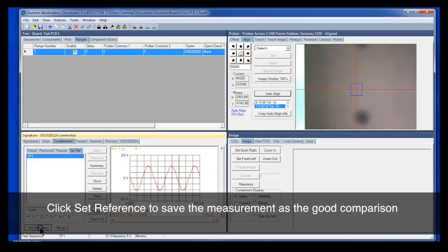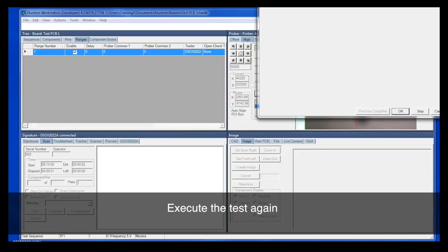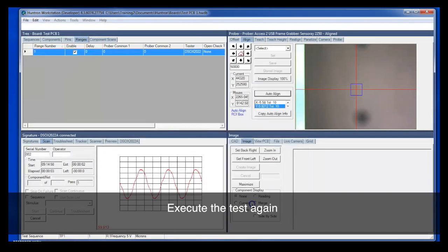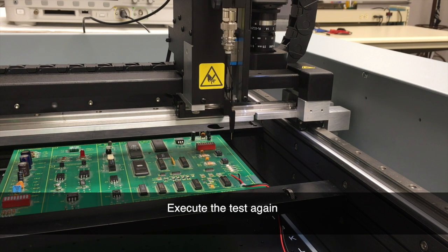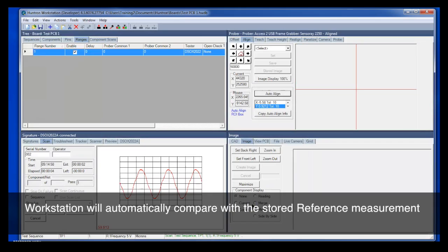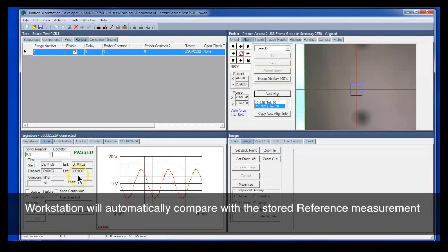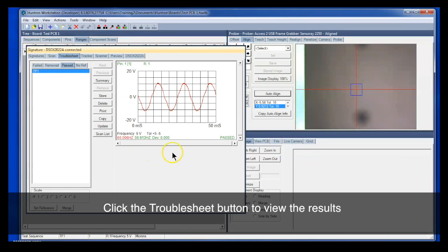So we'll set this as a reference. This will be now our comparison waveform and measurement. Let's run the scan one more time. Click OK to scan. Notice the probe goes and scans it. And we should get a pass indication. We do, because it was comparing to the same waveform. So if you open the troublesheet, there's our scan.